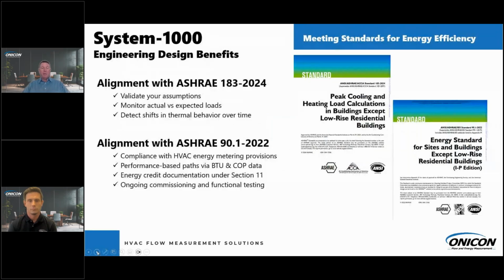Now, as we mentioned before, ASHRAE 183. We know there's a lot of new standards that are coming out right now that require you to meet standards for energy efficiency. The newest one is ASHRAE 183 2024, and that asks that you validate your assumptions. And with all the data from the System 1000, it helps you validate your assumptions. It asks that you monitor actual versus expected loads. Again, all the data in the System 1000 with your BTU performance can actually demonstrate for ASHRAE 183 what those actual loads are versus what you did in your load calcs. And then the continual monitoring that you can do with the System 1000 allows you to detect shifts in thermal behavior over time, and that keeps you also in alignment with ASHRAE 183.